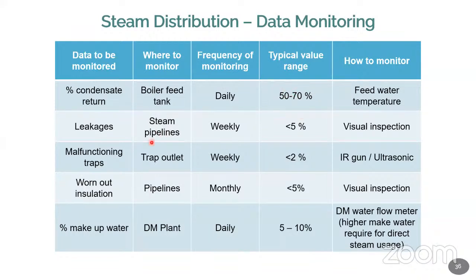Okay. Now the leakage should always be measured. Leakage in the steam pipeline and in the condensate pipeline should also be measured. That should be only 5%, and again it should be carried out by visual inspection. Trap functioning should always be measured. This is very important because when the trap is not working properly, the water will flow inside the steam pipe. Automatically that will affect the quality of the system. So you have to regularly check the trap.